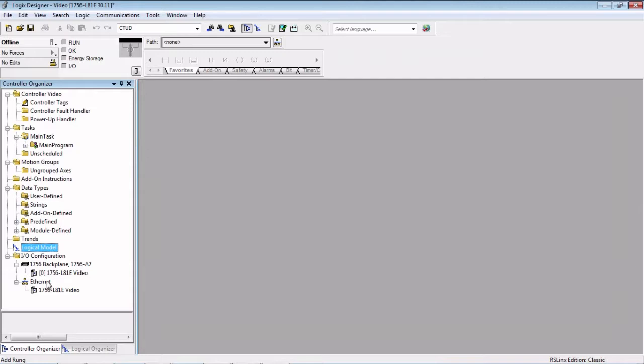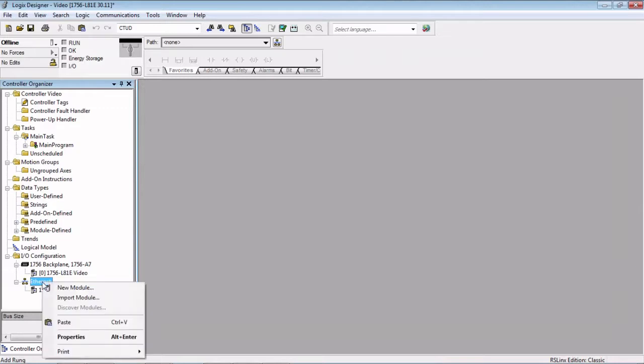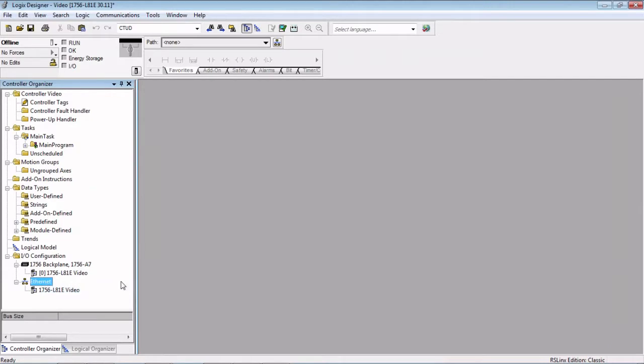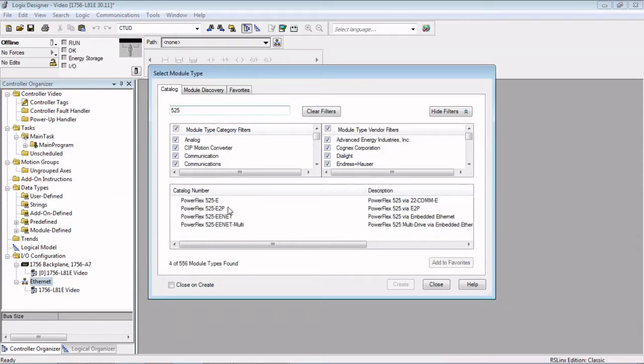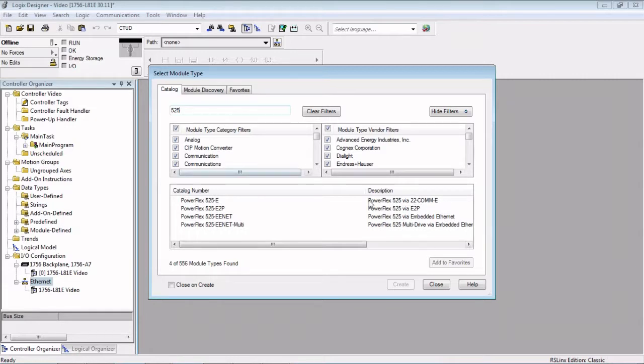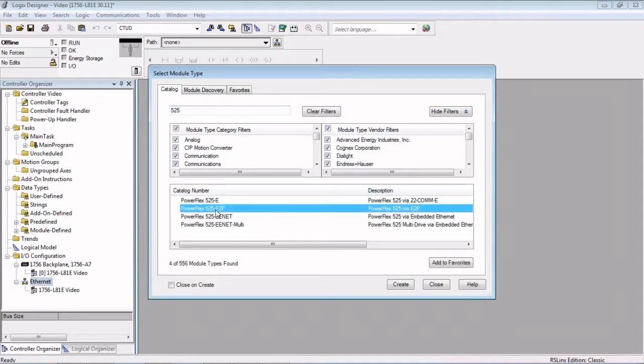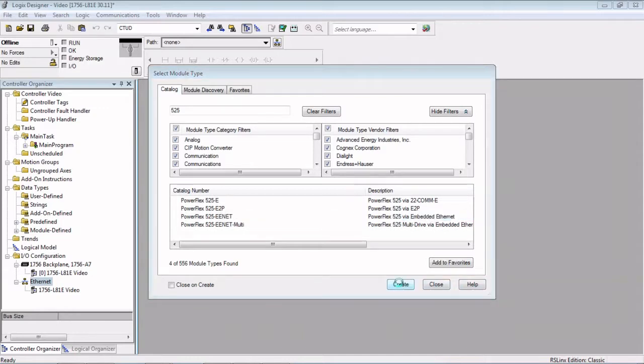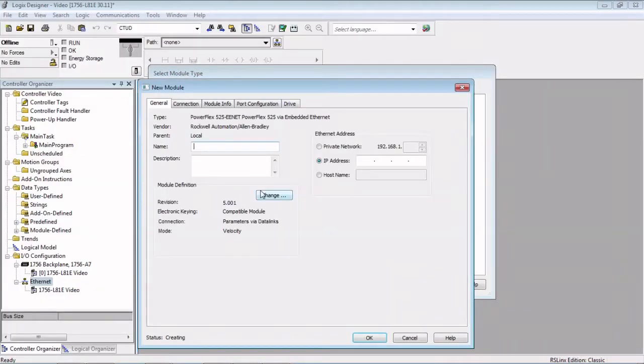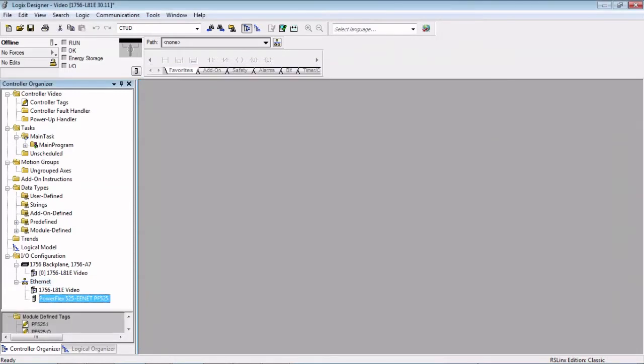Let's go ahead down here on our Ethernet. Since we're using L81E, it has an embedded Ethernet port, so we're going to use that Ethernet network. Right click and hit New Module. There's a couple options here for a 525. The 525 can use the 22-COMM-E which is the old style Ethernet card, but that does limit the amount of data that can go back and forth since it's older technology. There is a dual port Ethernet module available for the 525s. But we're going to go ahead and use the embedded Ethernet port on the 525. So we're going to add that, give it a name, PowerFlex 525 for instance, and an address. And we're going to hit OK and close this.